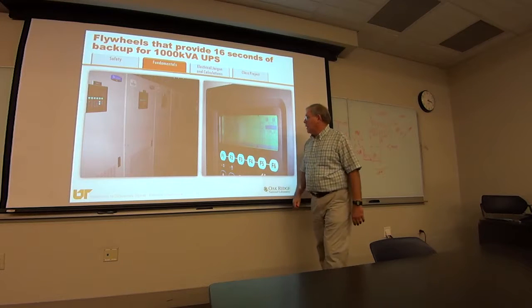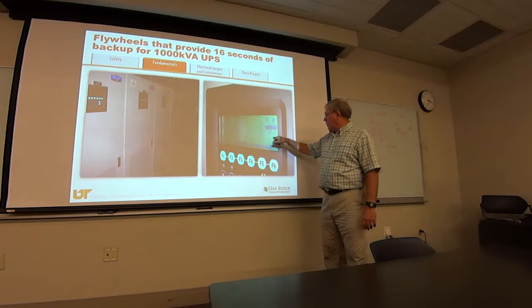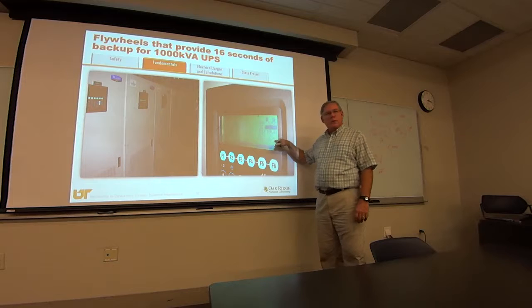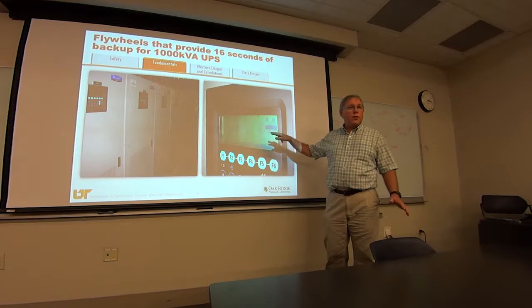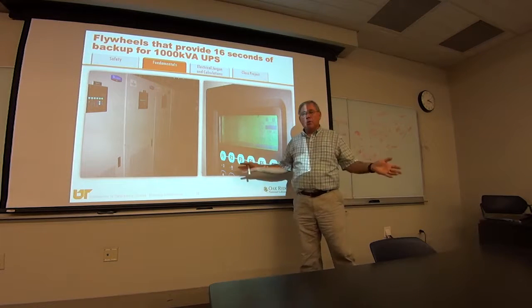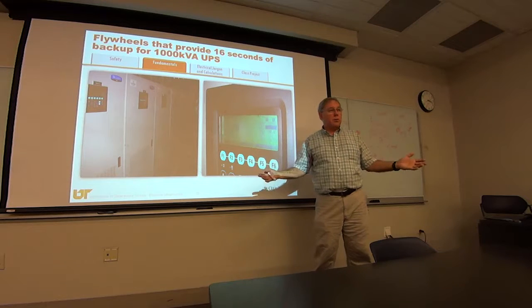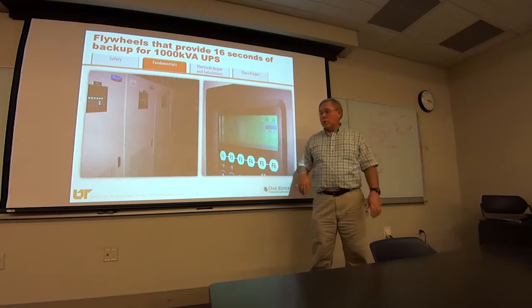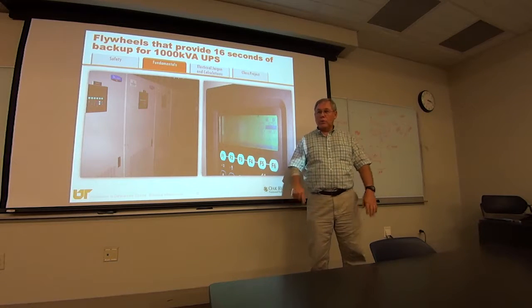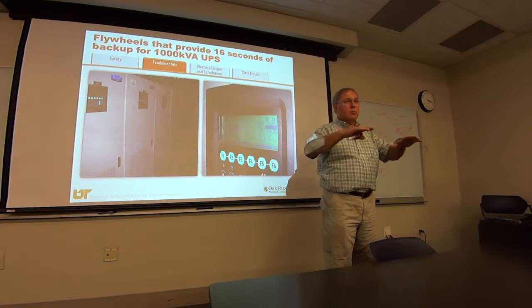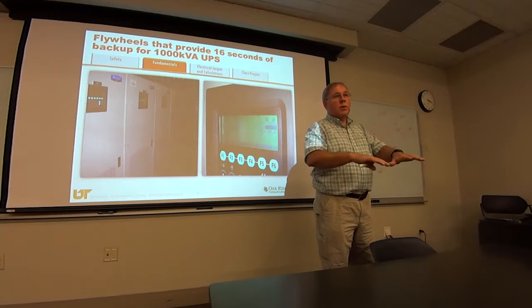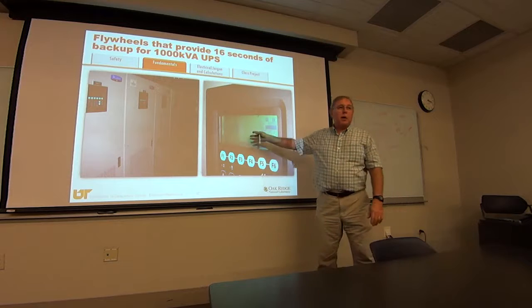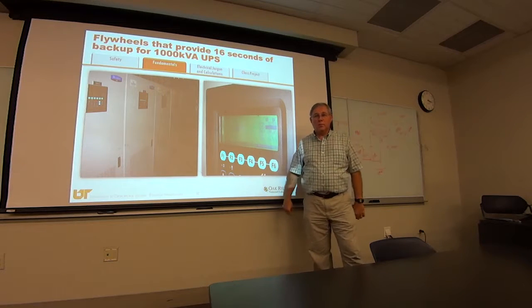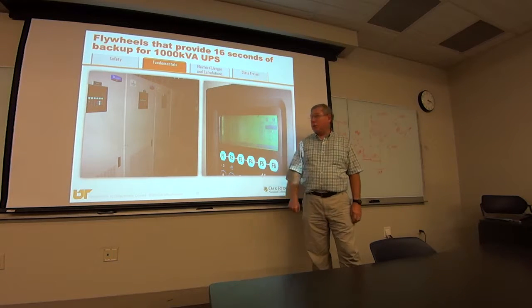And the beautiful thing about it is when they're running, they only draw 7/10 of a kW, 700 watts. They're very efficient, you don't have to replace them, you don't have to change the batteries every 5 years, they just sit there and run. Now, what you don't want to do is put them on a computer floor and have some guy drop a 3,200-pound computer cabinet right in front of one of them, because they're riding on magnetic bearings, and it messes up the bearings. We had that happen, by the way.